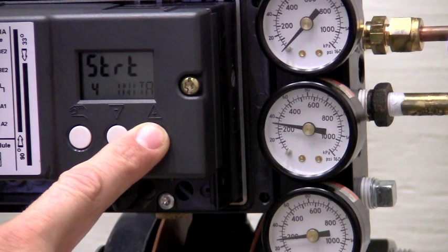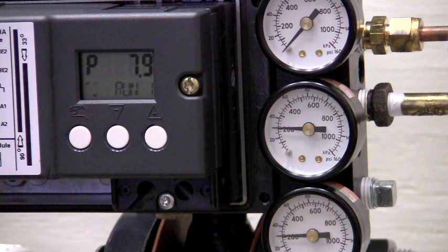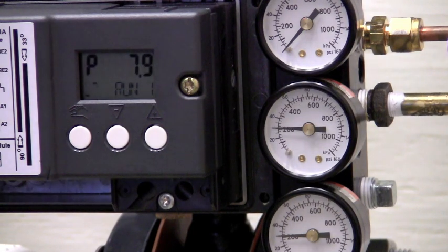The PS2 does the rest. It automatically finds the end stops of the actuator, sets the electronic range accordingly, checks for leaks in the tubing and actuator, and then goes into run mode.